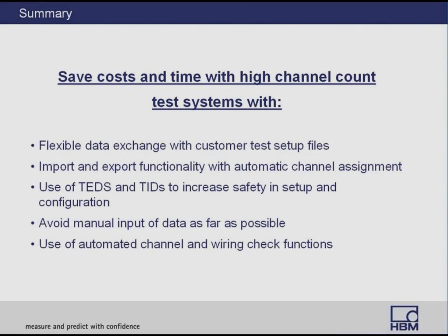I would like to sum up the previously discussed items by stating how to effectively increase the efficiency of large channel count setups. The important points therefore are: you need a flexible data exchange with customer setup files, import and export functionality with automatic channel assignment, use of TEDS and TIDs to increase safety in setup and configuration, avoid manual input of data as far as possible, use of automated channel and wiring check functions.